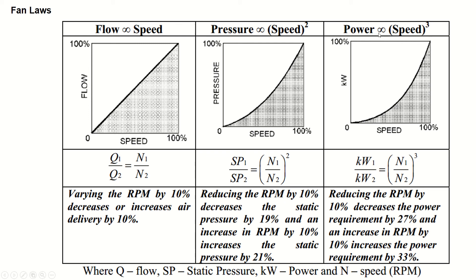The third fan law states that power is directly proportional to the cube of speed. Reducing RPM by 10% decreases the power requirement by 27%, and increasing RPM by 10% increases the power requirement by 33%.